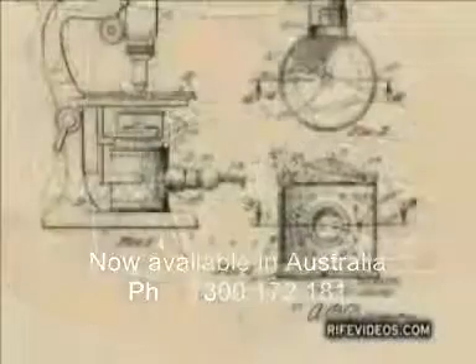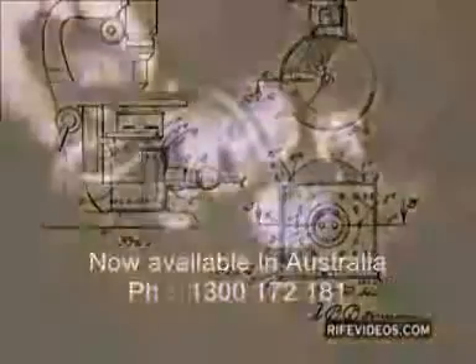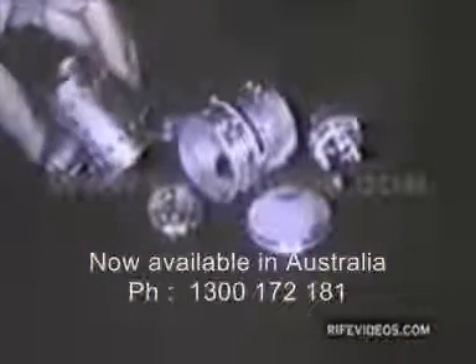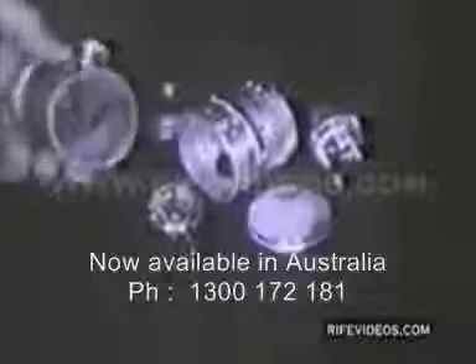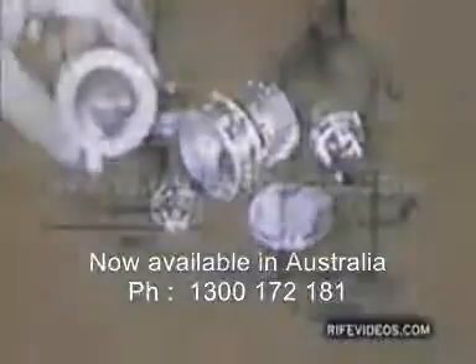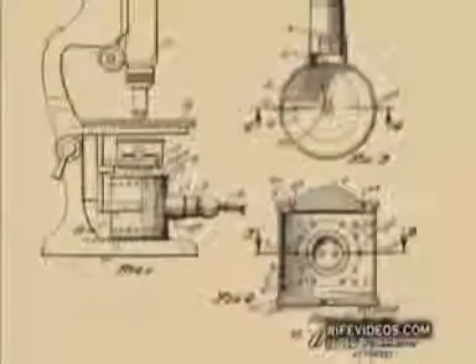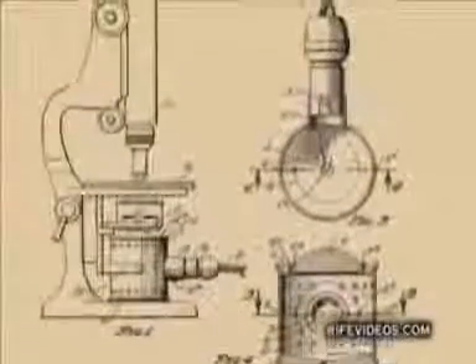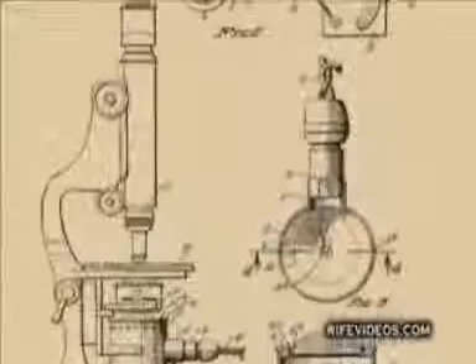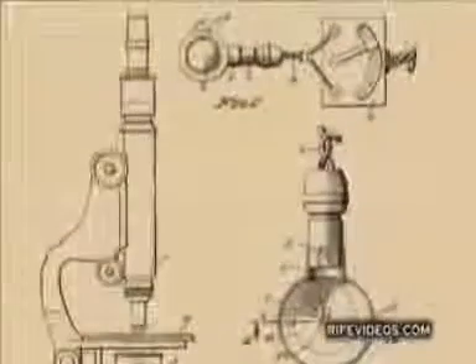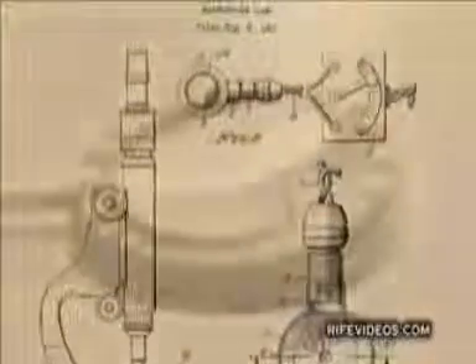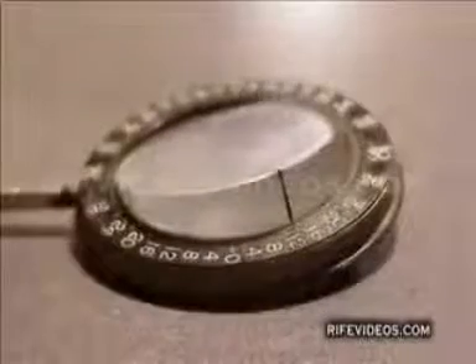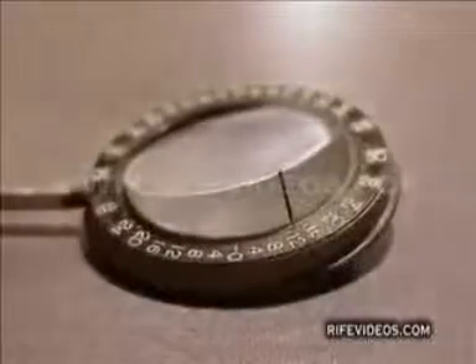We built a unit which I have a patent on, a special lamp that will produce 2,000 candle power and a needle point of beam where it comes through the condenser. But between this source of illumination and the so-called substage condenser, we have a pair. On the universal microscope we have 4, but we use a pair of rotating wedge-shaped quartz prisms. They're circular and they're wedge-shaped.